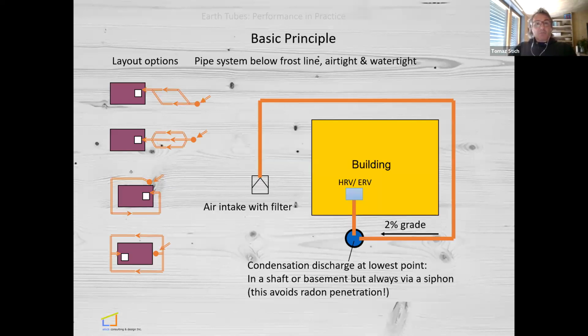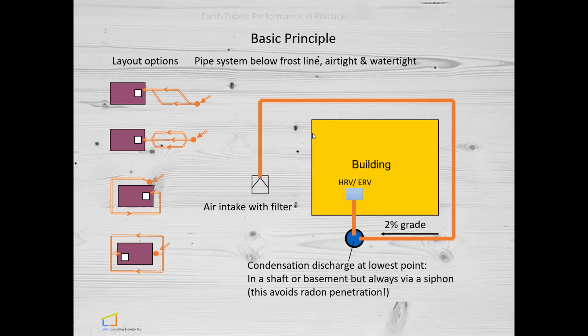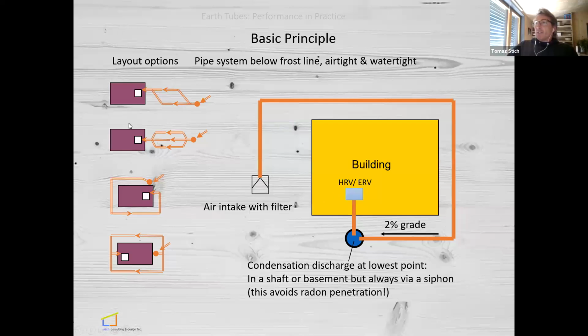Can you see my cursor, Frank? Yes, I can. Okay, so if you have a building here, HRV inside the building. On the left-hand side, you see some different schematics of earth tubes. It can be 2 pipes, 3, it can be 1 pipe. It doesn't have to be around the house, it can be 1 pipe. It has to be installed under a slope. And at the lowest point, you should have a condensation discharge just to prevent mold and condensation.